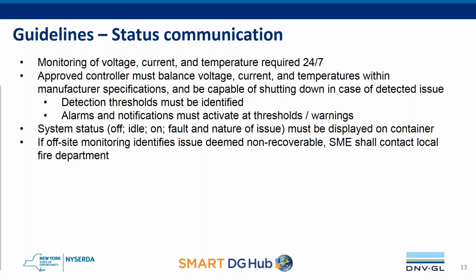This last item, if the offsite monitoring identifies issues deemed non-recoverable, the subject matter expert shall contact local fire department, is one of the areas where we're determining how it's best to proceed forward with that contact. But again, the key feature here is to know what the ranges of optimal operation are and safe operation are, and if it goes beyond those and is not recovered, i.e. if the temperature is rising and it does not stop rising, that the appropriate AHJ is contacted.